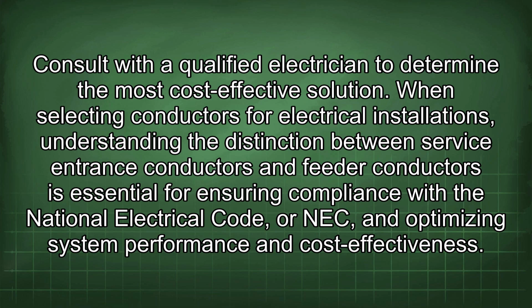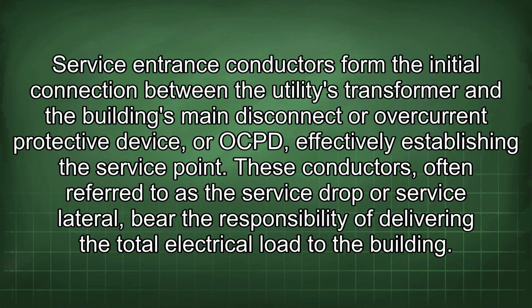When selecting conductors for electrical installations, understanding the distinction between service entrance conductors and feeder conductors is essential for ensuring compliance with the National Electrical Code, or NEC, and optimizing system performance and cost-effectiveness. Service entrance conductors form the initial connection between the utilities transformer and the building's main disconnect or overcurrent protective device, or OCPD, effectively establishing the service point.